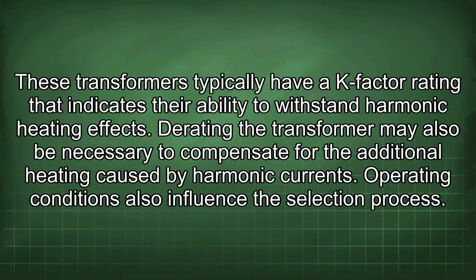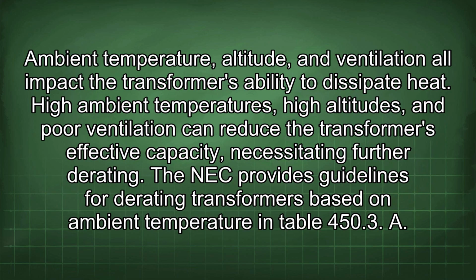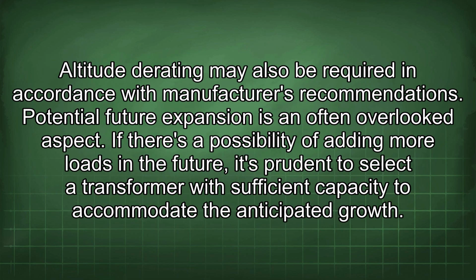Operating conditions also influence the selection process. Ambient temperature, altitude, and ventilation all impact the transformer's ability to dissipate heat. High ambient temperatures, high altitudes, and poor ventilation can reduce the transformer's effective capacity, necessitating further derating. The NEC provides guidelines for derating transformers based on ambient temperature in Table 450.3. Altitude derating may also be required in accordance with manufacturers' recommendations.